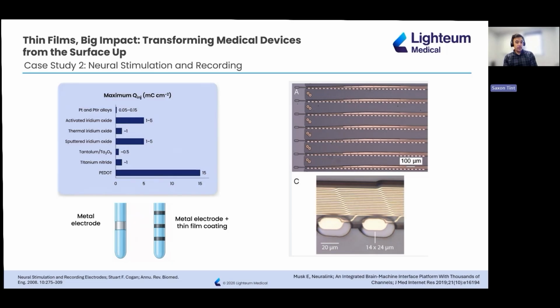This is what allows us to build arrays like the one shown on the right. Hundreds or thousands of tiny electrodes, each small enough to talk to a very localized group of neurons independently. And this is a prerequisite for things like adaptive deep brain stimulation or functional stimulation after a spinal cord injury, and ultimately brain-machine interfaces like the Neuralink electrode array, which is shown on the right of the screen. So none of these systems are possible with bare metal electrodes. It'd simply be too noisy or too large and unable to inject enough charge safely. It's the thin film engineering at the surface that enables electrodes small enough, sensitive enough, and safe enough to interface with the nervous system at the level of individual neurons.